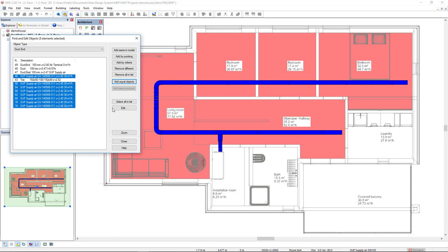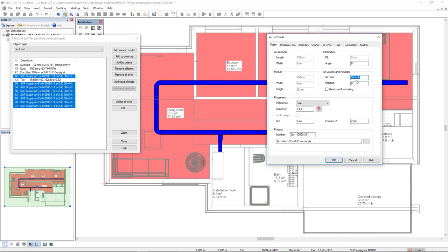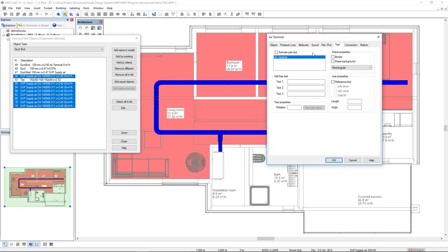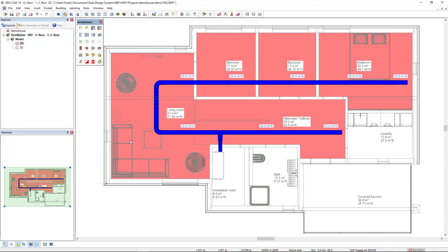I'll click on the edit option. And now we can see that this air terminal has a maximum airflow of 330 cubic meters per hour. This is what we want to know from this tab. And in the tab text, I will activate the part text. And I will also erase the background. And I'll click OK and close. Here they are.